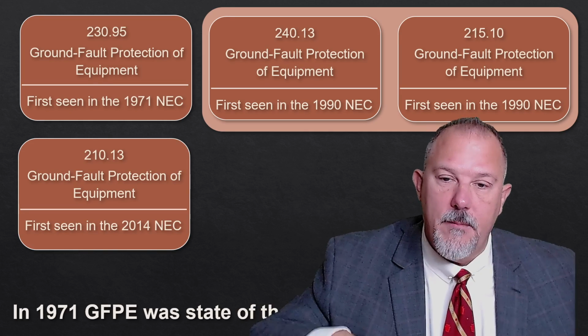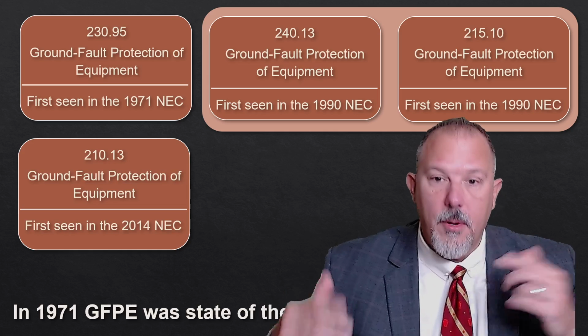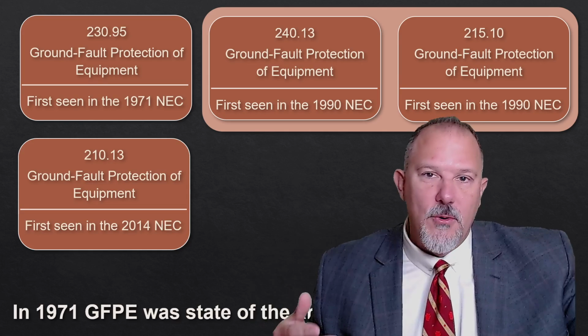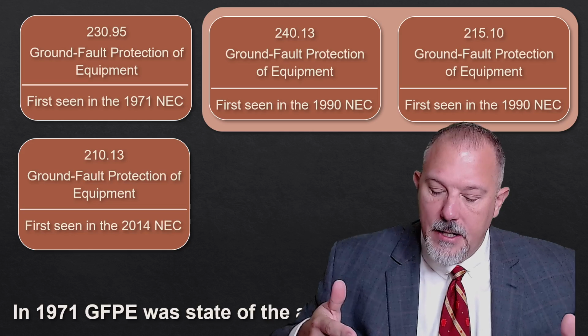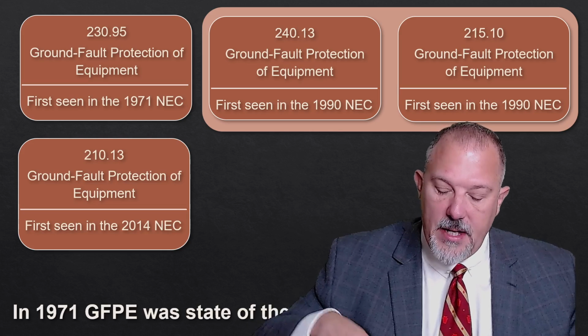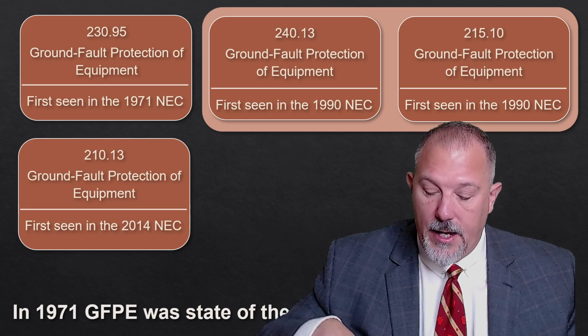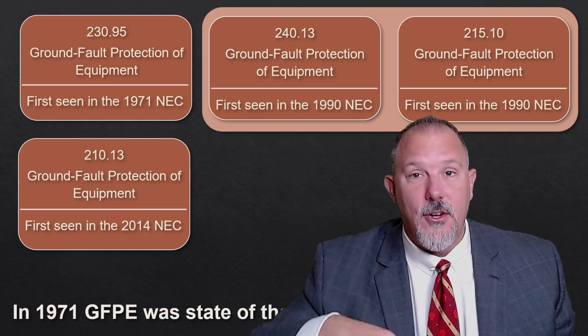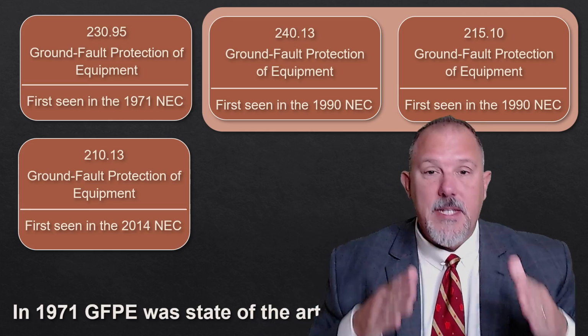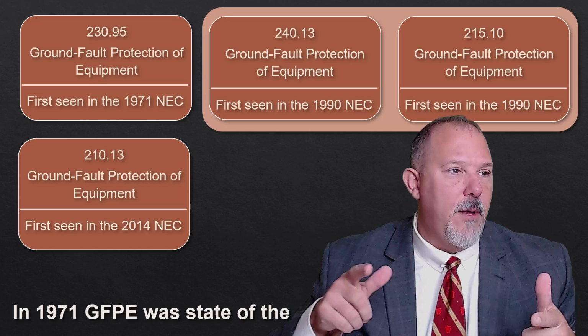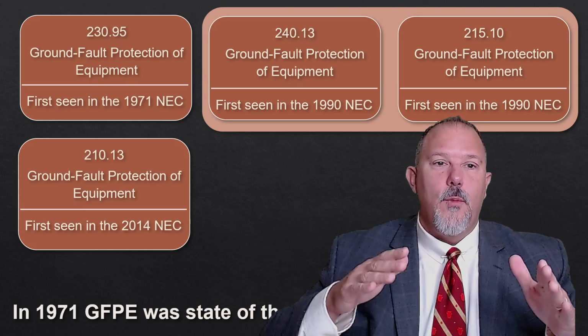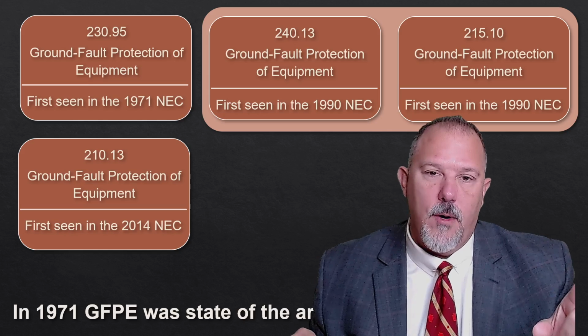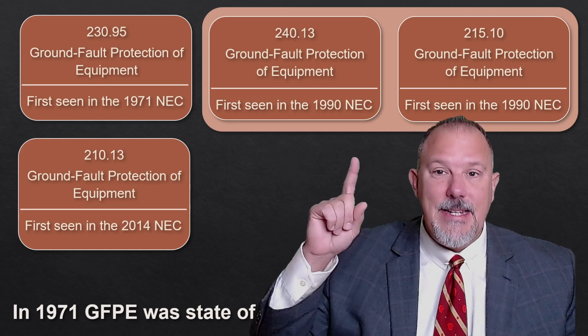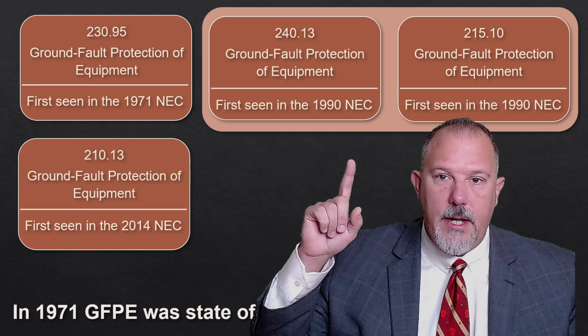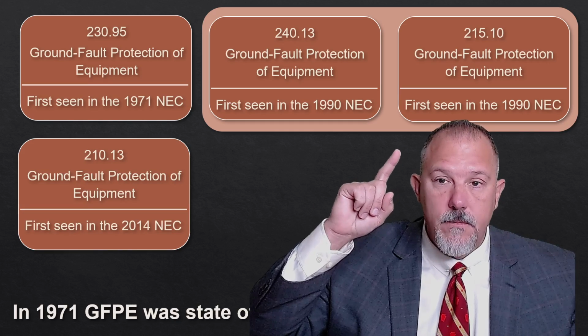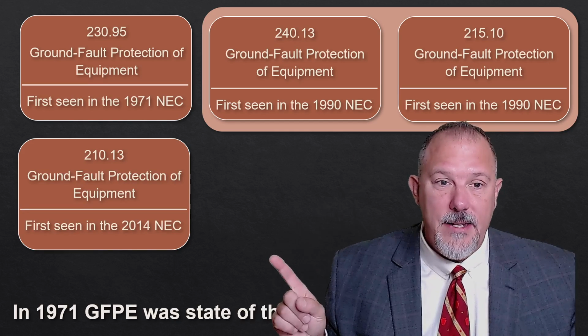with this public input proposal, right? Report on proposals we had in the past, report on comments. The proposal here was to add GFPE, which was added in the '71 code, and it was because of the arcing faults that occur inside of equipment. Now, we'll get into the details on that one. So 230.95 went in in 1971, and it wasn't until 1990 that they added it in 240 and in 215 for feeders.